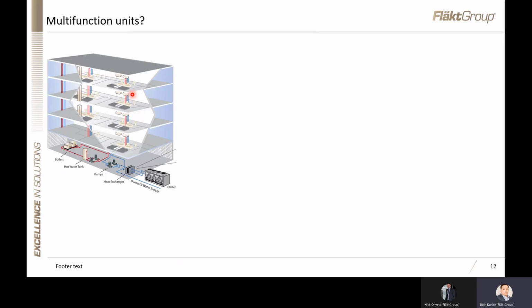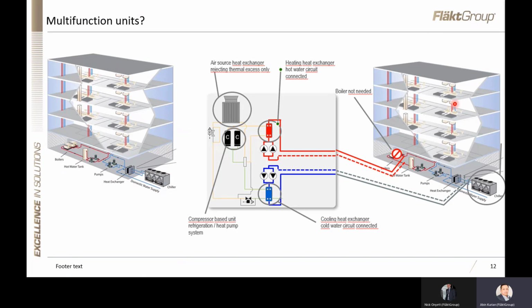Now I would like to introduce you to our multifunction unit. So what is a multifunction unit? In this figure, you can see the traditional way of how we design a building. You have a chiller and a boiler. The chiller serves chilled water to your fan coil units and the boiler serves hot water to the fan coil units. Instead of this, we are proposing a new heat pump, called a multi-function heat pump, that can provide simultaneous heating and cooling solutions. So you can get rid of the boiler within the building, and this single machine can provide heating, or heating and cooling simultaneously.